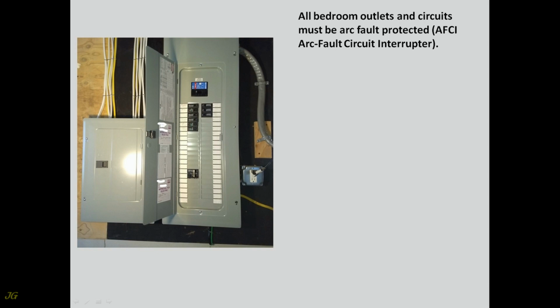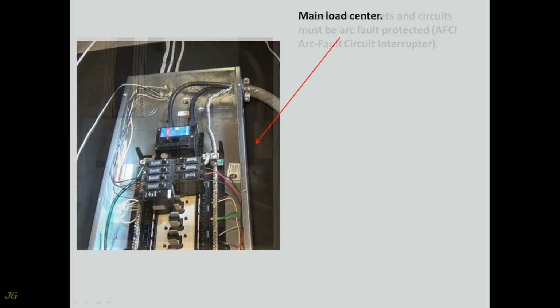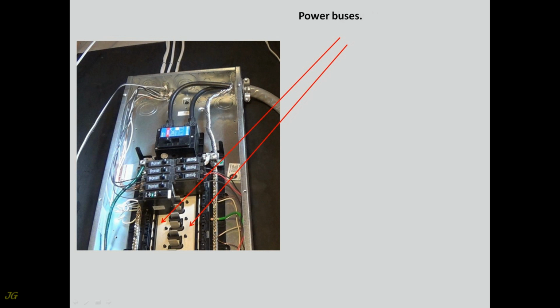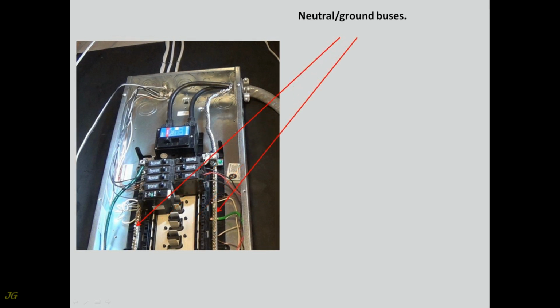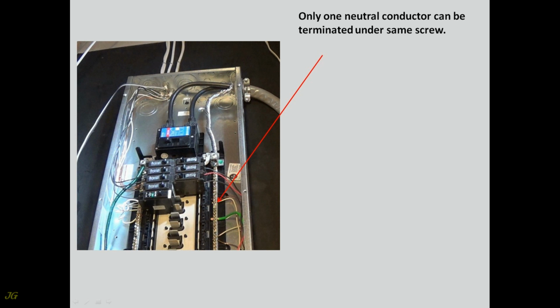AFCI, arc fault circuit interrupter. Main load center. Power buses. Neutral, ground buses. Plug-on neutral buses. Main breaker. Branch circuit breakers. Load center bonding screw. Only one neutral conductor can be terminated under same screw.